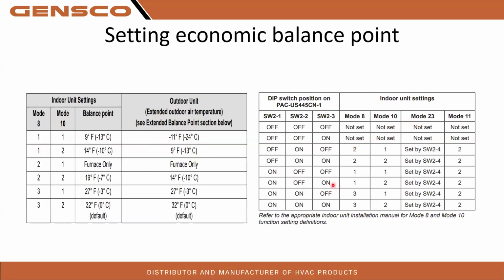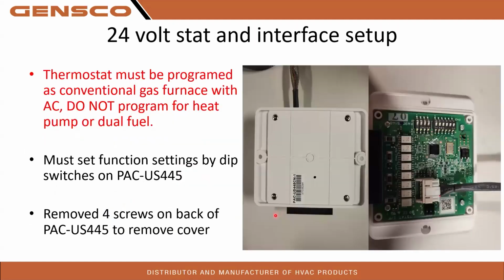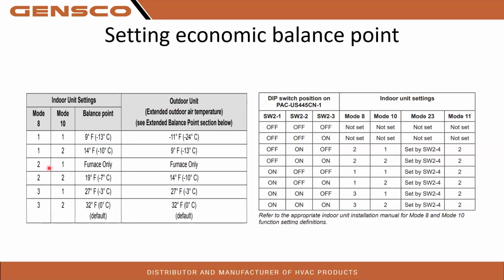If you're using a PAC 445 and you're using dip switches, you're going to need both of these charts pretty much. Because you need to know what function mode you want to set your temperature to and which dip switches you need to set to do that. For example, if I want to set for 32 degrees, which is the default, but on the PAC 445 you have to turn them on anyways. If I want a 32 degrees changeover balance point, then mode 8 would need to be set to 3 and mode 10 would need to be set to 2. So you come over to your chart here, mode 8, 3, mode 10, 2. That tells me my SW2 switch 1, 2, and 3 should all be on. And that is this dip switch bank right here. So if I wanted to make it furnace only, mode 8.2, 10.1, only SW2 switch 2 would be on.